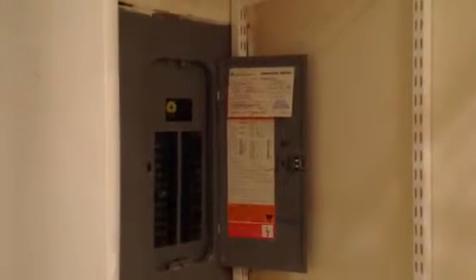The main electrical service panel is currently located in the master bedroom closet wall here. A few things with the panel. One, electrical panels are no longer permitted in closet locations. Two, it doesn't have proper clearance around the panel.